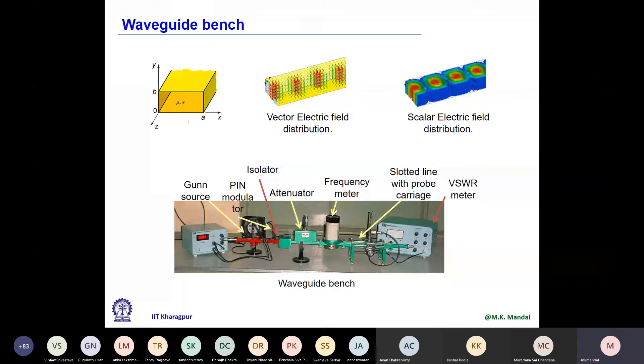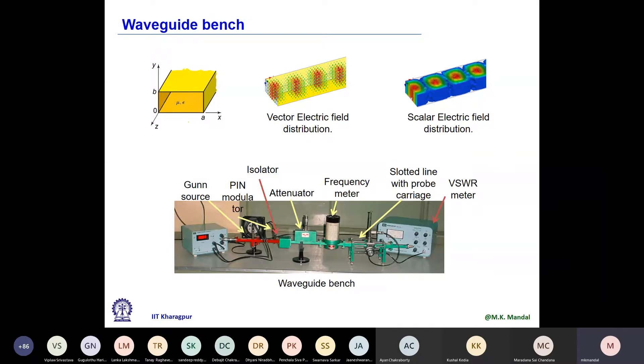After the source, we have different components: a PIN modulator, which basically works like a switch — on and off — then an isolator, next an attenuator, and a frequency meter for measurement of source frequency. Then there is the slotted line with probe carriage. At the other end, you will be connecting a load, short circuit, or antenna — whatever you are going to measure. In addition, we have another instrument called the VSWR meter, which can directly measure voltage standing wave ratio inside the waveguide section.